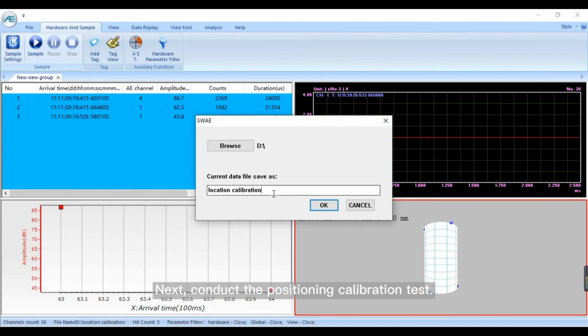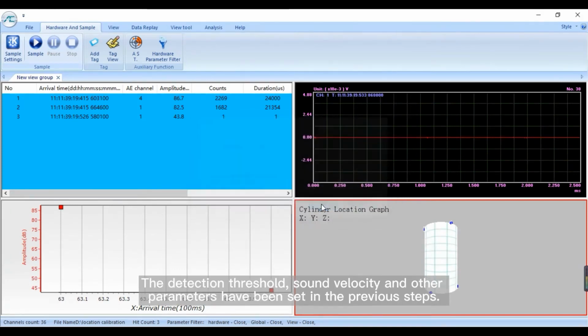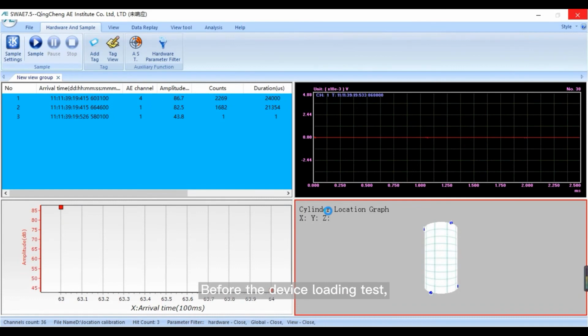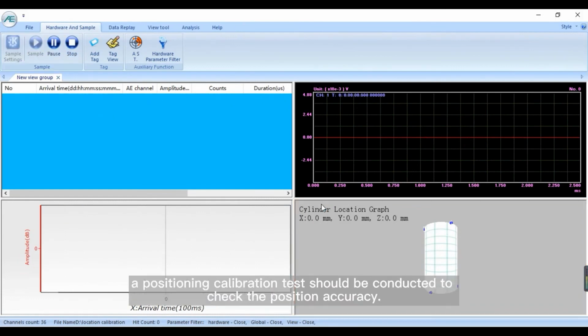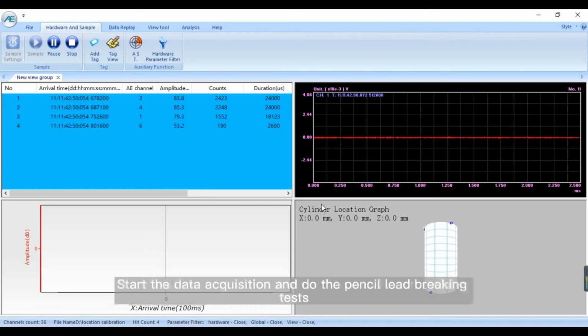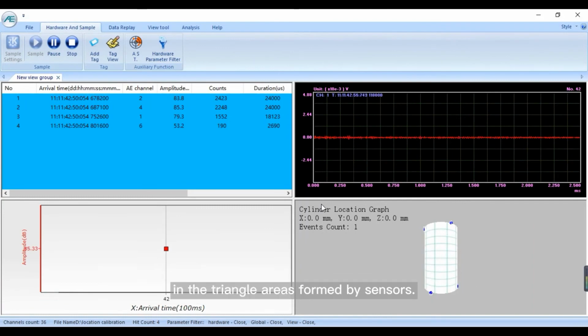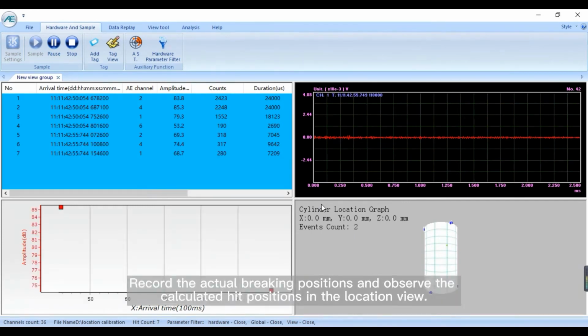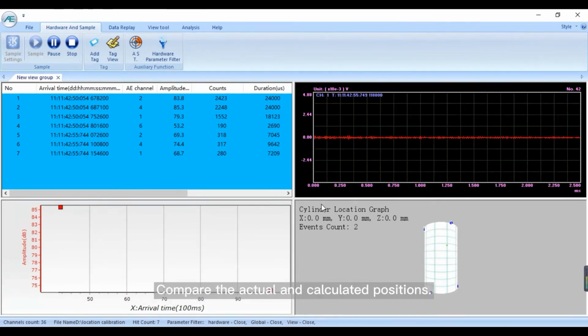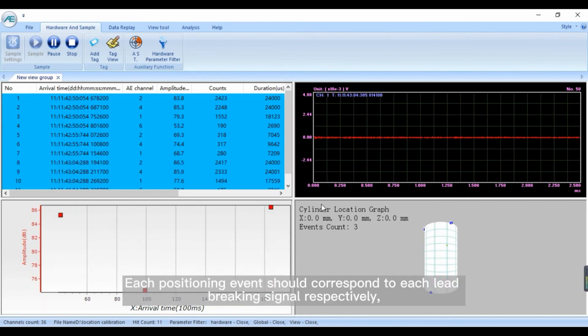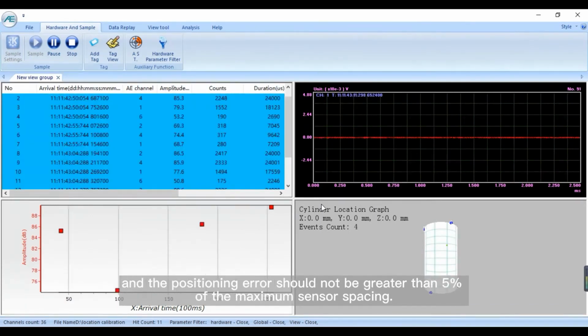Next, conduct the positioning calibration test. The detection threshold, sound velocity, and other parameters have been set in the previous steps. Before the device loading test, a positioning calibration test should be conducted to check the positioning accuracy. Start the data acquisition and do the pencil lead breaking tests in the triangle areas formed by sensors. Record the actual breaking positions and observe the calculated hit positions in the location view. Compare the actual and calculated positions. Each positioning event should correspond to each lead breaking signal respectively, and the positioning error should not be greater than 5% of the maximum sensor spacing.